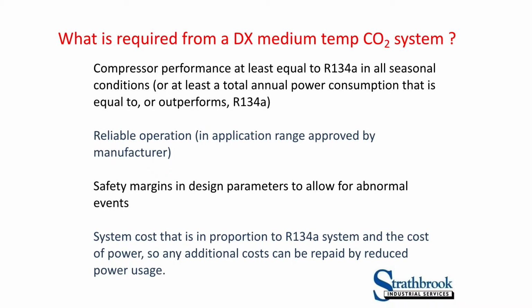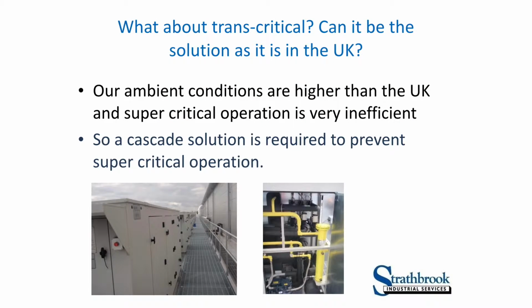So we looked at what was done overseas, because Sainsburys and different people had already done transcritical CO2 cascaded to subcritical. And when we looked at what they did, they just put a massive number of units out there and put a lot more capacity in than needed to cope with the real hot days. The problem is that in the UK, the really hot days are 35, not 45. And they're very few and far between. A heat wave over there goes for a week, and it's not a heat wave that we would understand.